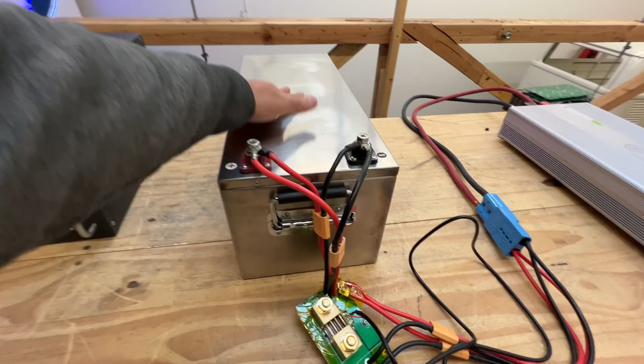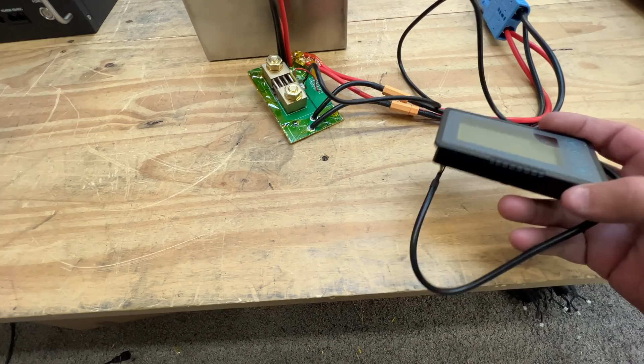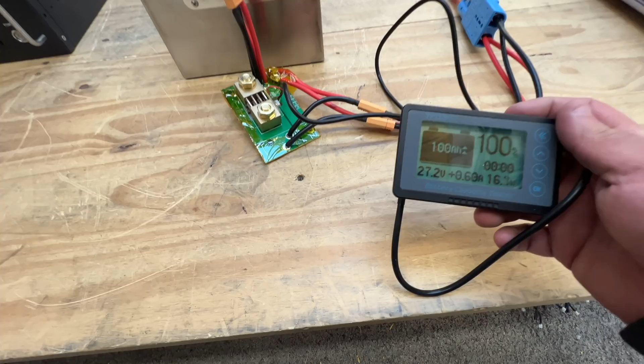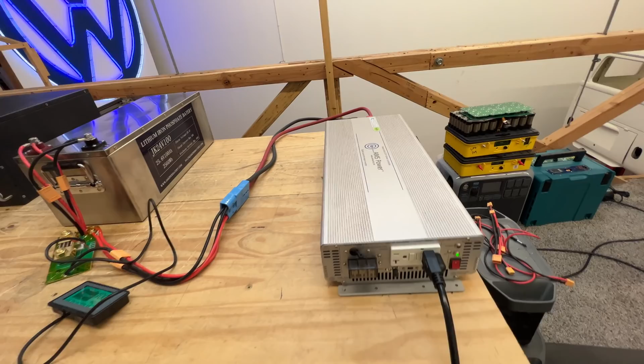All right, time to do the capacity test. I have this 24 volt battery connected via this shunt, which is just a current or battery meter that keeps track of the battery. It's right now at 100 amp hours, 100% state of charge - it's got this blue light. My load is going to be this Ames 3000 watt, 24 volt inverter.